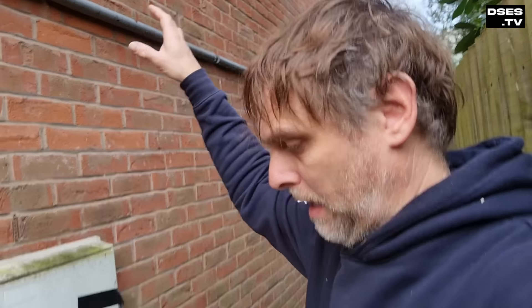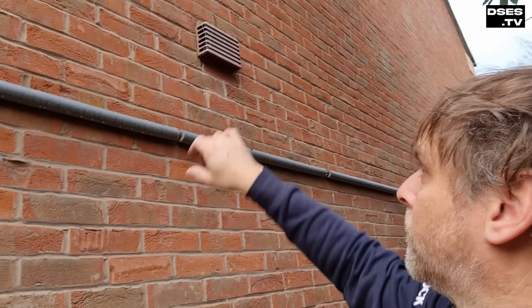For me, I'm going to have to drill out the back of that CU to get a cable out here, because we appear to be looking at a failed cable in the wall, which is unusual. You don't see many cable failures in walls. The only time I've really come across one before is where there's been subsidence — I've seen subsidence put strain on a cable and break it — but there's no obvious answer as to why. There's power just on the other side and no power down here. So I'm going to have to get a new cable out, which means drilling out through the back of that CU. Then I'm going to have to get around this shonky water pipe to get a new feed down, thinking some black plastic conduit after the kick over the pipe.